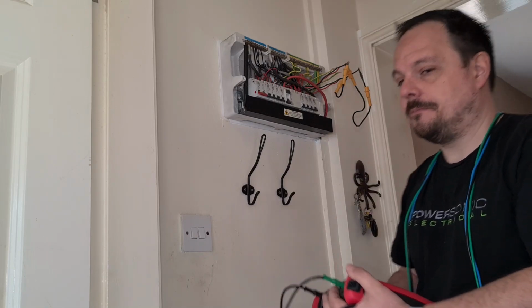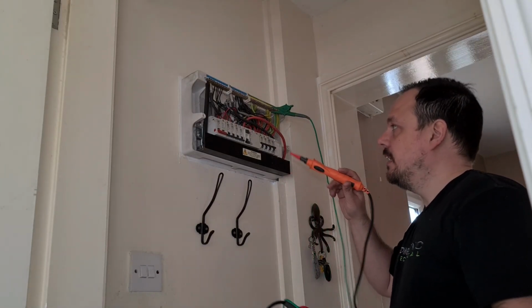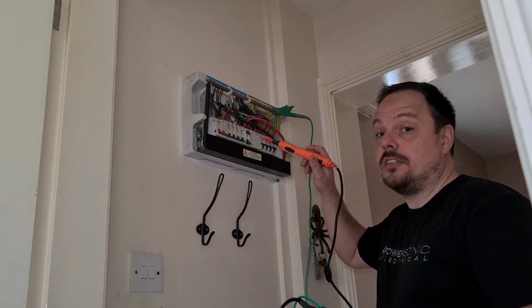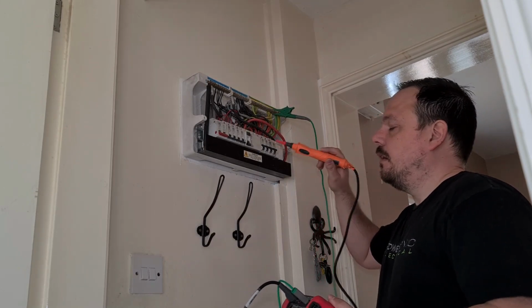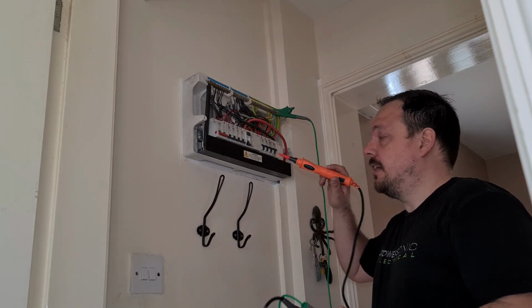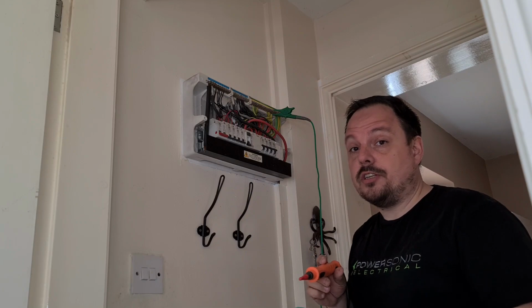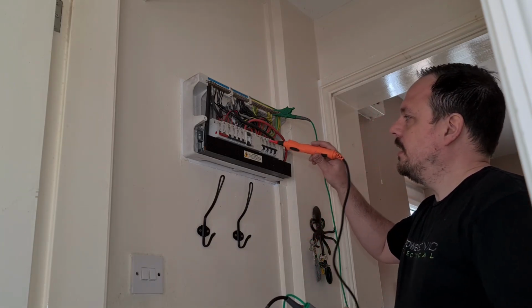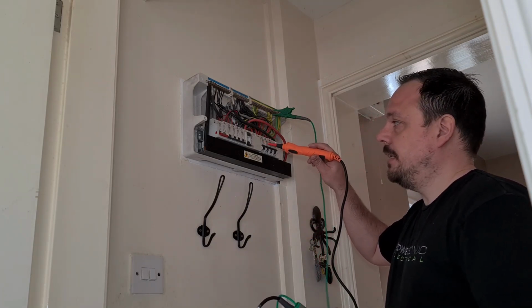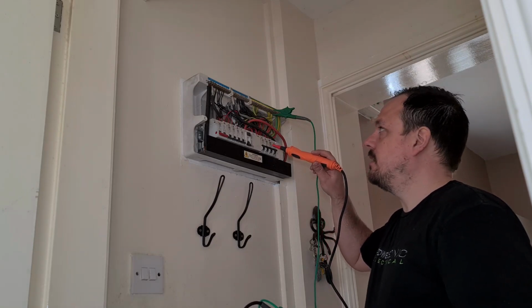So with the sockets on the IR testing, well, I say it's the sockets, it's the cooker as well. Obviously we can do that with all of the loads disconnected. We're unplugged, got the cooker switch in the off position. We can then turn all of these MCBs on. Obviously the power's still off, this is a dead test.